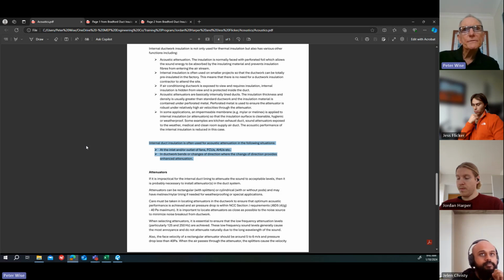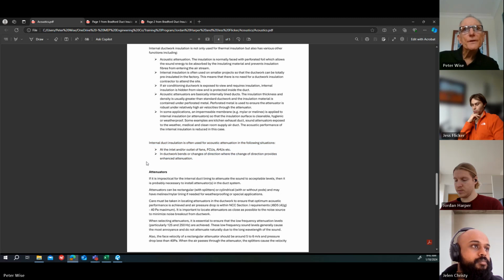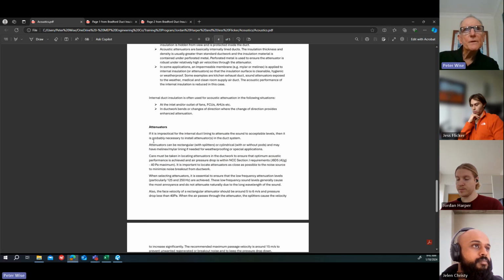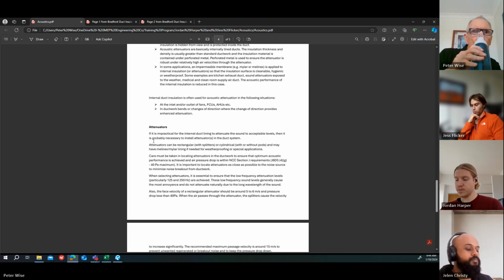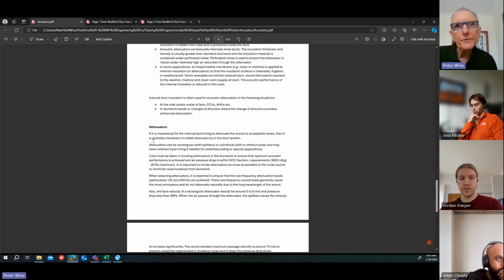Internal duct insulation is often used for acoustic attenuation in the following situations. At the inlet and or outlet of fans, fan coil units, air handling units. I'm sure you've come across this already. And quite often in ductwork bends or changes of direction, where the change of direction provides enhanced attenuation. So that's just a quick summary of internal insulation of ductwork. Any questions on that?